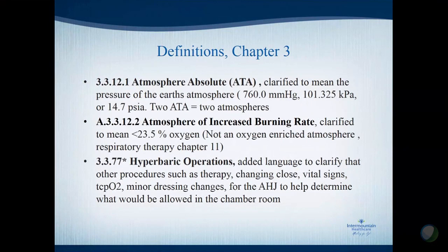So you skip from Chapter 1 to Chapter 3. Chapter 3 contains all the definitions, and definitions are important because the words that we use have real meaning. For example, in the 2015 edition, we added a definition for qualified. In other words, who's qualified to do the testing and maintenance and all of that for our chambers. So we added a word definition in Chapter 3.